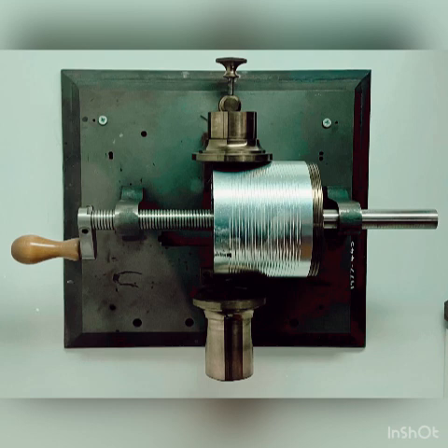Occluded ear simulator, Zwislocki coupler. Ear simulator: device for measuring the output sound pressure of an earphone under well-defined loading conditions in a specified frequency range, consists essentially of a principal cavity, acoustic load networks, and a calibrated microphone. Location of microphone is chosen so that the sound pressure at the microphone corresponds approximately to the sound pressure existing at the human eardrum. It has 4 adjustable side resonators. Don't get artificial ear mixed up with occluded ear simulator, 2 different things.